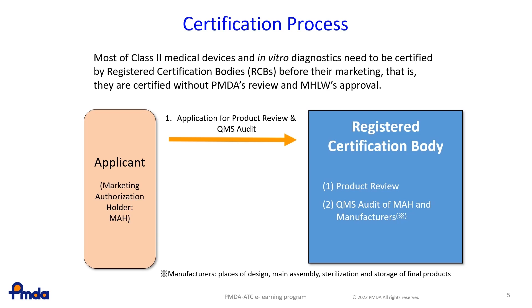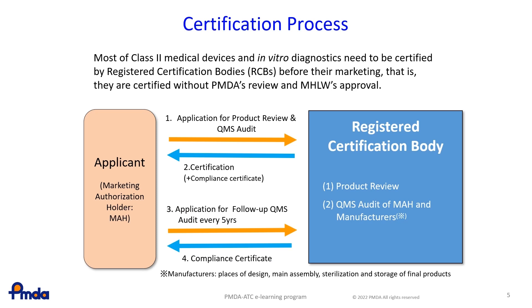The RCB conducts product review and QMS audit on the MAH and manufacturers and determines whether they meet all the requirements. If they do, the RCB issues a certification of conformity to the requirements and the MAH can market the product. The MAH and manufacturers are required to be audited every five years after certification.